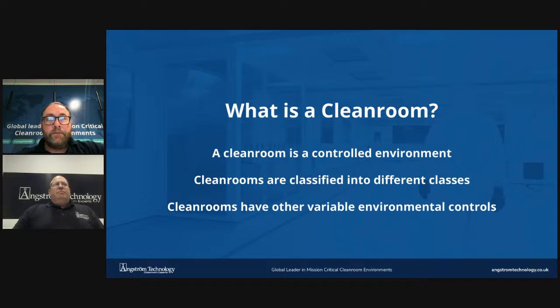So a clean room is a room within which the concentration of airborne particles is controlled and which is constructed and used in a manner to minimize the introduction, generation and retention of particles inside the room. Other relevant parameters such as temperature, humidity and pressure are also controlled as necessary. Clean rooms are classified into different classes depending on the number of particles allowed in the air per cubic meter, and two standards are generally used to classify them, those being ISO 14644 Part 1 2015 and the EU GMP standard.